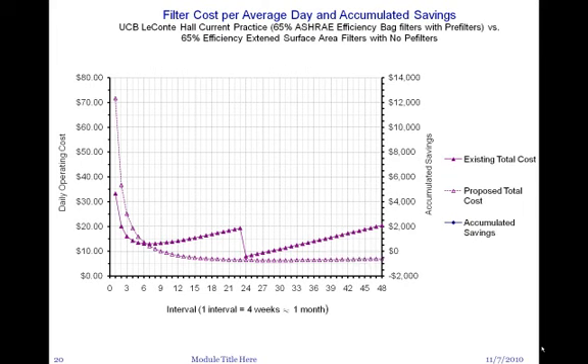I've actually built spreadsheets to model this where we use loading rates — we model loading rates based on field data collected from a number of sites. For instance, this is a project in Berkeley. That's a plot of how they were initially running: bag filters with pre-filters, changed every two years, and that's where the little bump in the curve is. We proposed eliminating the pre-filters and using a more expensive final filter that had much lower clean pressure drops and a flatter loading characteristic. And that's what its modeled characteristic looks like, based on field data for a similar filter.